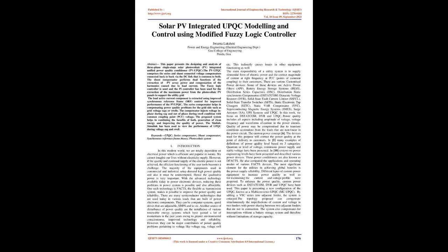The load active current component is extracted using improved synchronous reference frame, SRF, control for improved performance of the PV-UPQC. The series compensator helps in compensating power quality problems for the grid side, such as grid voltage sags or swells. The compensator injects voltage in phase during sag and out of phase during swell condition with the point of common coupling, PCC, voltage.